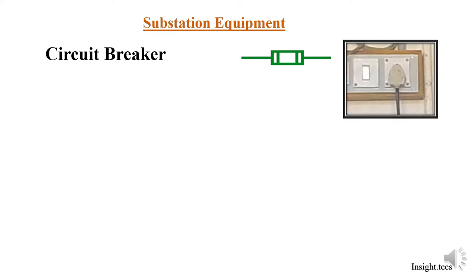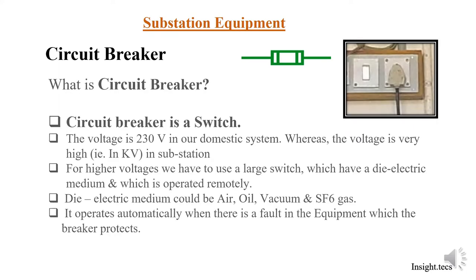A circuit breaker is basically a switch. At our home we have 230 volts in the domestic system, so the switch can do the making and breaking of the circuit. However, the voltage levels are in kilovolts for the substation, so for higher voltages we have to use a larger switch which has some dielectric medium and which can be operated remotely from the control room. Dielectric mediums such as air, oil, vacuum, or SF6 gas are used in circuit breakers. It operates automatically when there is any fault in the equipment which the circuit breaker is protecting.